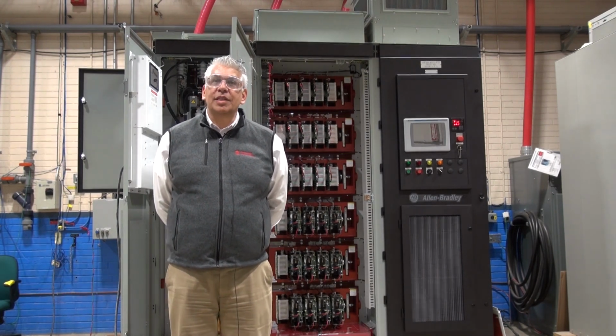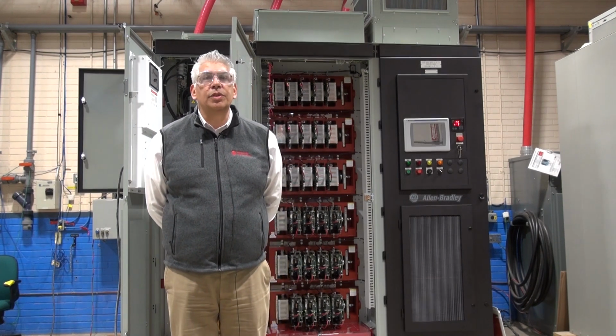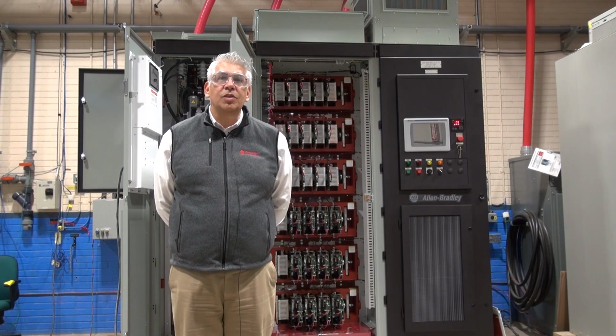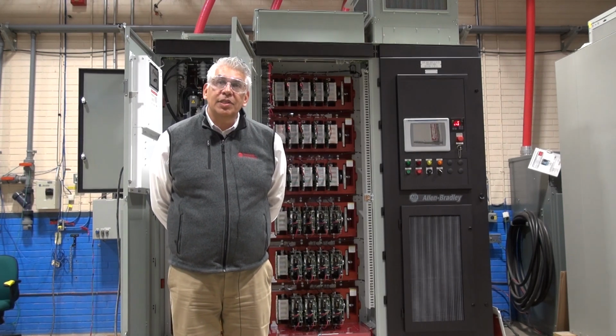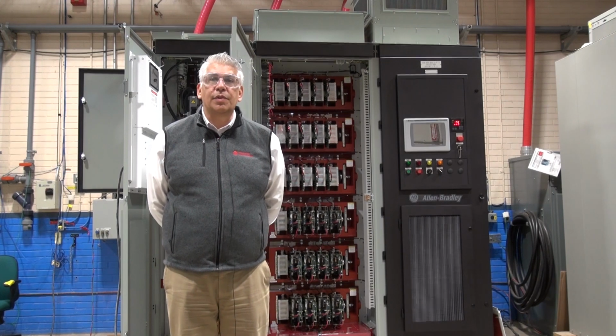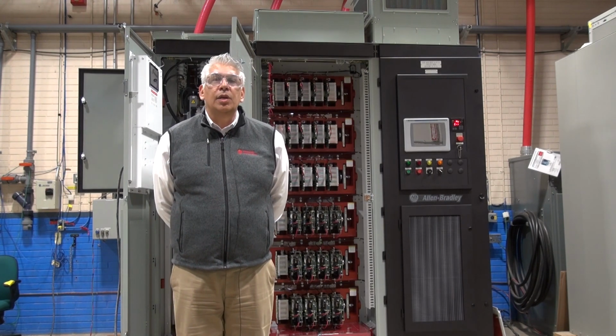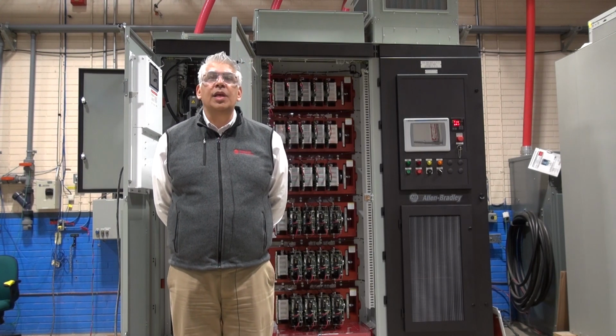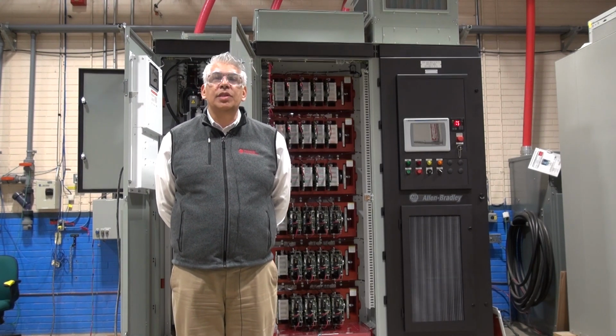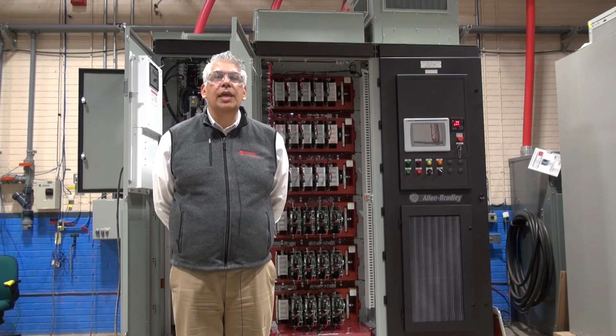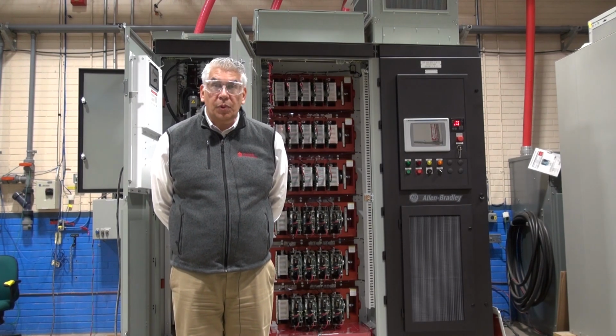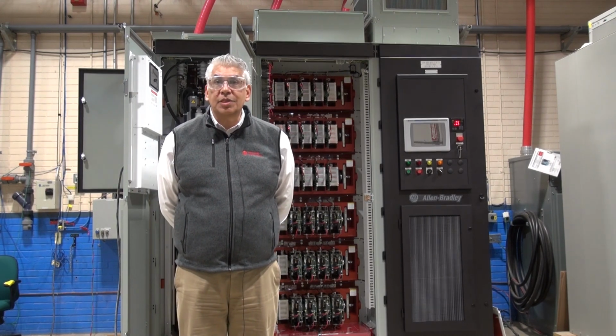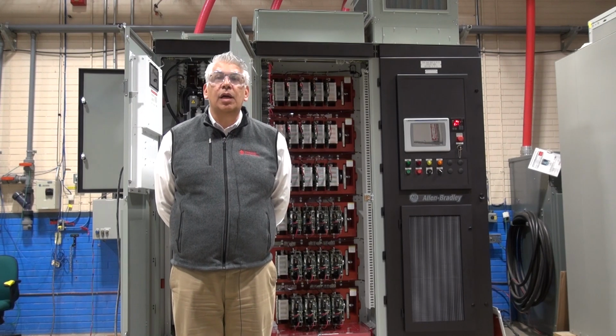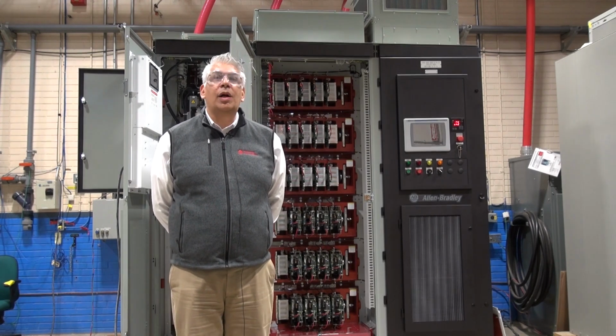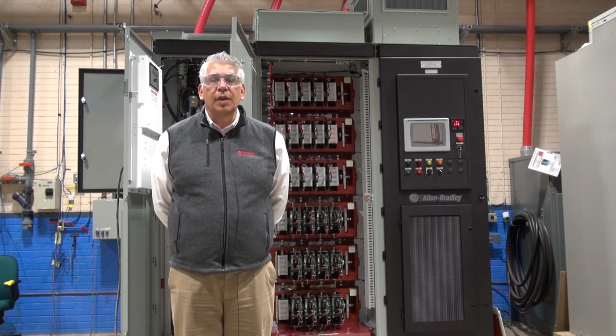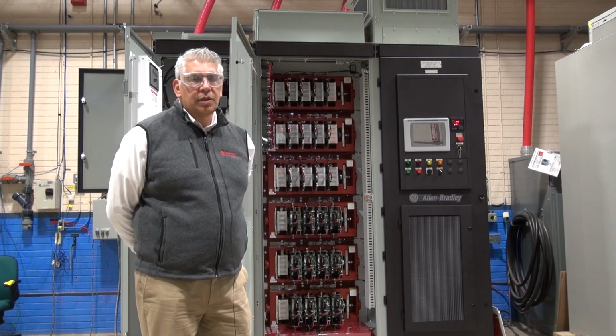We also have a PowerFlex 6000 product line that is targeted towards general purpose applications such as fans, pumps, and compressors. I'm going to talk today about what we call our special purpose drive, the PowerFlex 7000, that's really targeted towards cranes and hoists, downhill conveyor applications, any applications that require either regen braking or regenerative operation, or potentially holding torque at zero speed, and also extremely long motor cable lengths because of this specific topology and the benefits that it offers. So a couple of things that I just want to focus on.